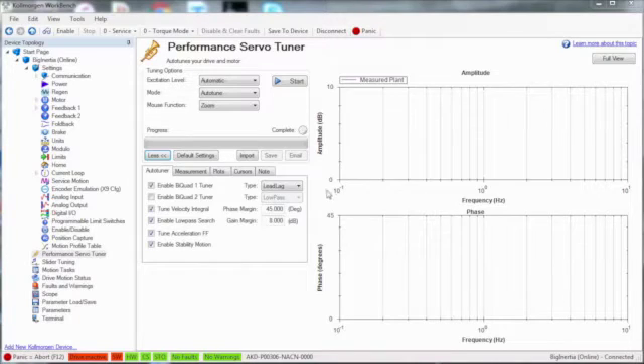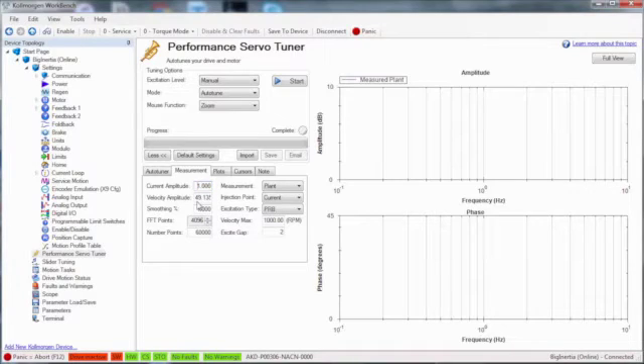In the measurement tab, start by setting excitation current manually. The level was set to 1 amp, in our example. This is about 50% of the motor's continuous current rating.